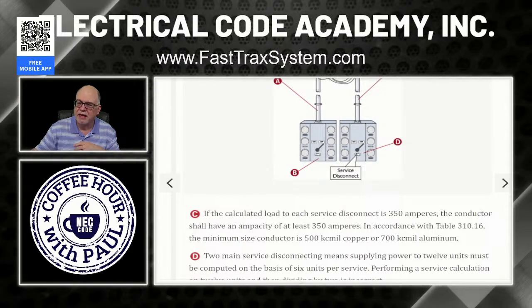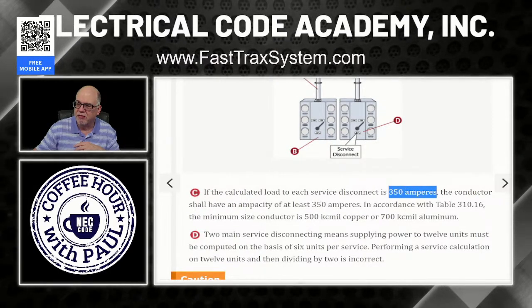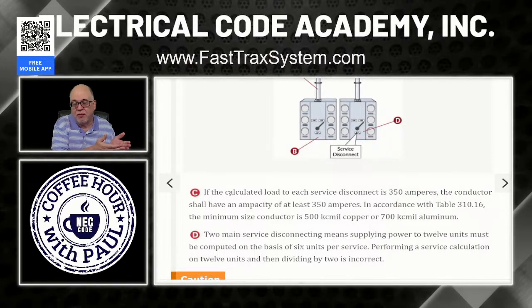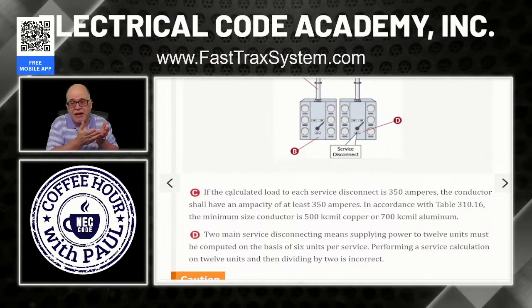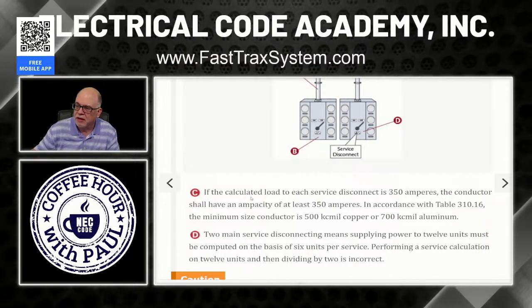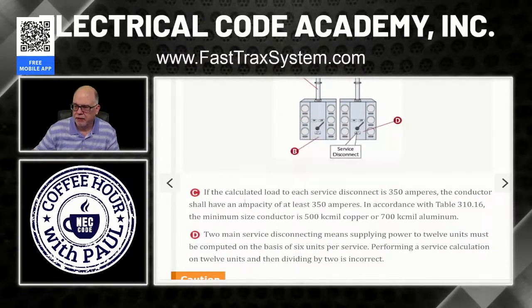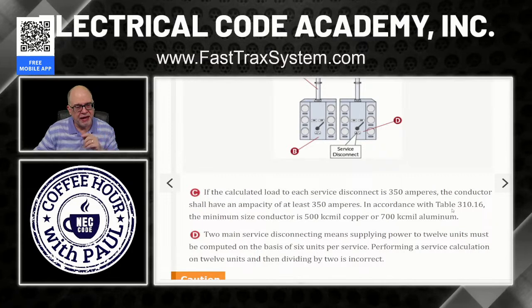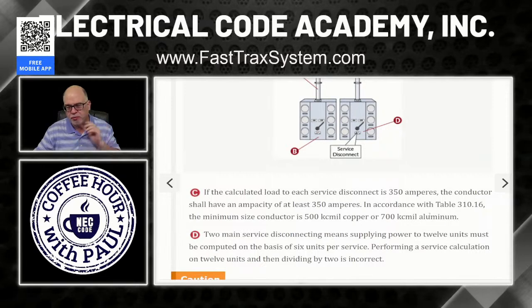So if the calculated load for each service disconnect is 350 amps, okay, so that's what we calculated out. And that's what we determined the size of the service disconnect to be, right? We did a load calc, whatever it was, and that's how we sized our service disconnect, okay? Makes sense. Now, it says the conductors shall have an ampacity of at least 350 amperes, in accordance with Table 310.16, the ampacity table you heard me talk about before. Again, we can't use 310.12. This wouldn't apply. So we're going to use the full ampacities from the table.